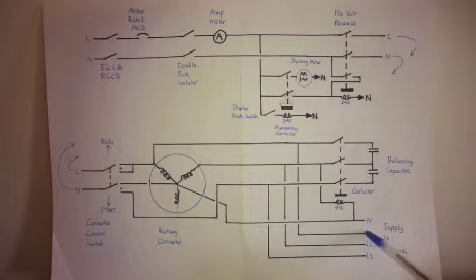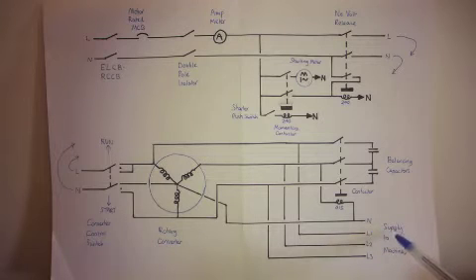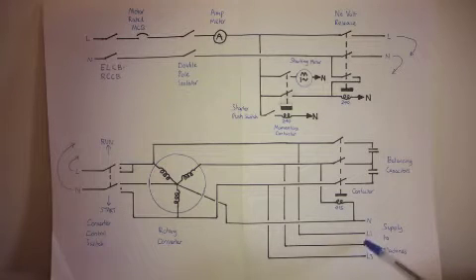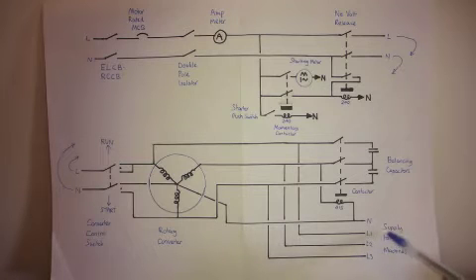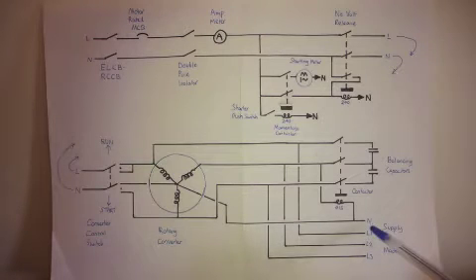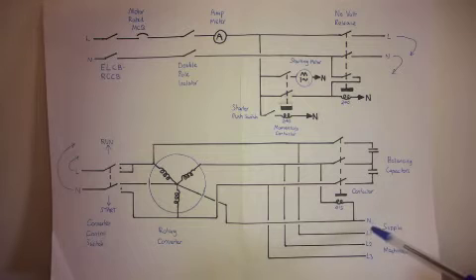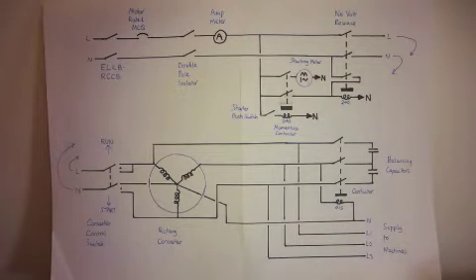Also, I've used that strongest phase there to run the lighting transformers from, and the two false phases are just dealing with the other two phases on the three-phase motor and all the additional loads of the contactors and lighting transformers are all on L1.